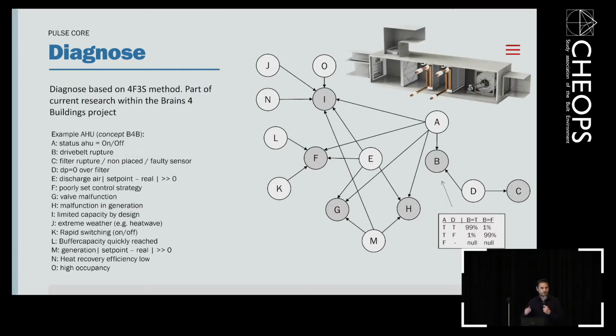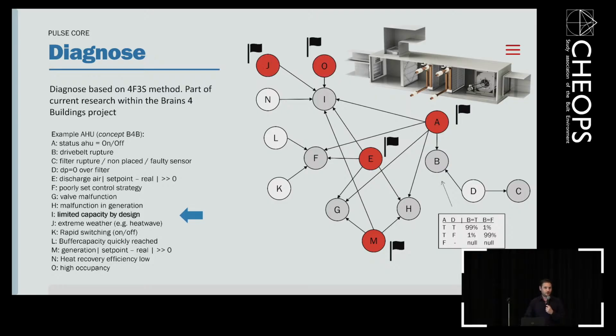The same idea can be applied to air handling units: if the inlet temperature is the same as it's set to, then it's okay. But let's say the inlet temperature is different than you want, and you also see that the supply temperatures were in line—then probably there's something wrong with one of the valves. If you have the same conditions, but there's also extreme weather and many people present in the building, maybe it's more like a limited capacity by design.